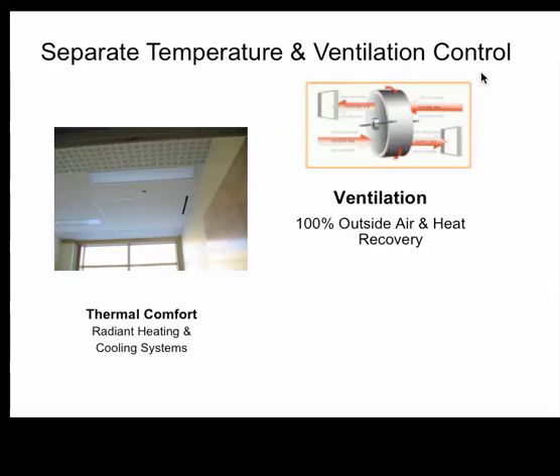Once we take care of the loads, we're able to design smaller, simpler systems. In our climate, we've gone with 100% outside air with heat recovery using enthalpy wheels, at 1.5 air changes, as opposed to VAV systems which require 6 air changes - so significantly smaller air systems.